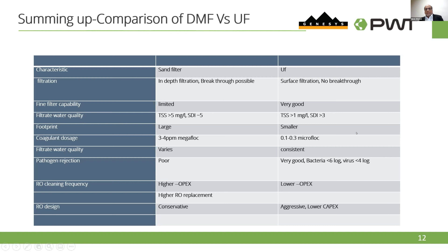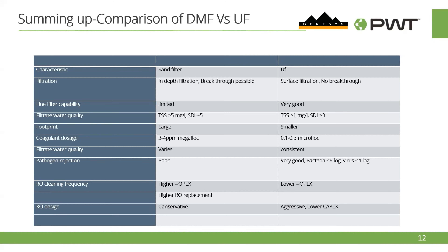Filtered water quality: TSS in UF can be less than 1 ppm and SDI less than 3. Footprint is large for sand filters whereas UF is smaller. Coagulant dose for sand filter requires 3 to 4 ppm, whereas UF requires only 0.1 to 0.2 ppm. As a result, RO cleaning frequency will be higher with sand filtration and lower with UF.